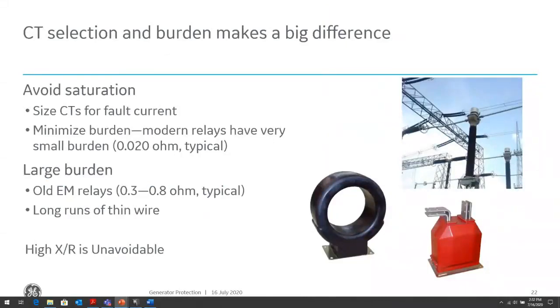and that can cause the generator differential to trip erroneously. With microprocessor relays, burden so much is not a concern anymore, because microprocessor relays are very low burden to CTs. Electromechanical relays had large burdens. Most of the burden when you talk about microprocessor relays will be in the CT wiring from the generator relay out to the CT. So that's a very long distance, and you want to have large gauge CT wires, like 8 to 10 gauge CT connections, so you can reduce the burden. What we cannot avoid is, if our system has a high X over R ratio, we cannot avoid pushing the CT into the saturation region quicker. So the things that we can control are the burden and the CT sizing.